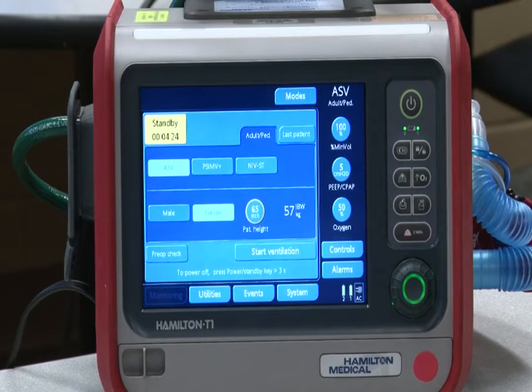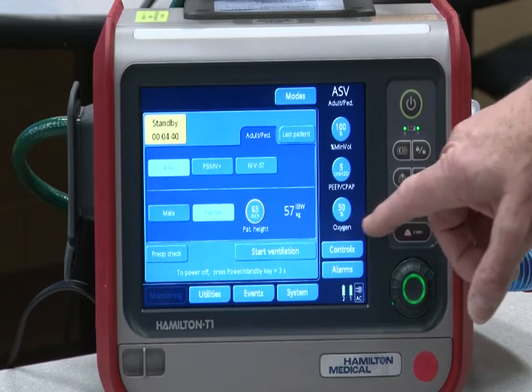So if you wanted to change the patient's FiO2, let's do that, because our vents, yours probably came up at 50%. So I programmed them so that it would, that's right in the middle, so you don't have as far to turn it. So when we get to using the vent, if we don't turn that to room air, we're going to get alarms because we're not hooked up to anything. So let's all turn our FiO2 down to room air.